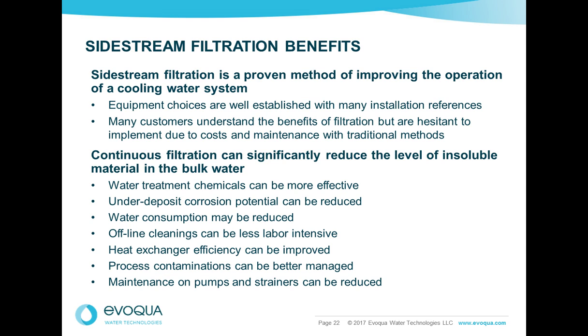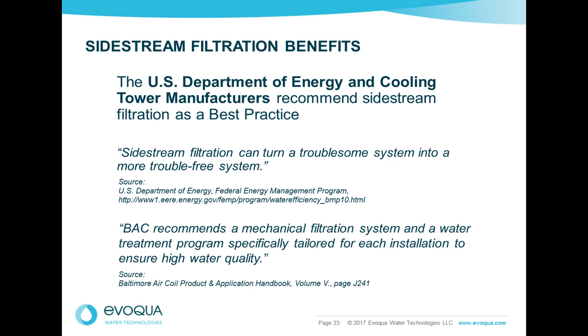Sidestream filtration. Sidestream filtration is the easiest way to take a difficult system and make it into a better behaving system. There's a variety of equipment choices, installation places. Generally, we're talking about filtering between 3 and 5% of the recirculating flow, and that'll really make the system operate much better. Continuously filtering can significantly reduce insoluble materials in the bulk water. The water treatment chemicals are more effective. Under deposit corrosion goes away. Water consumption is reduced because your blowdown's reduced. Blowing down a cooling tower to get rid of the dirt is not nearly as effective as filtering the dirt out. It's also cheaper because you stop throwing away all the chemicals.